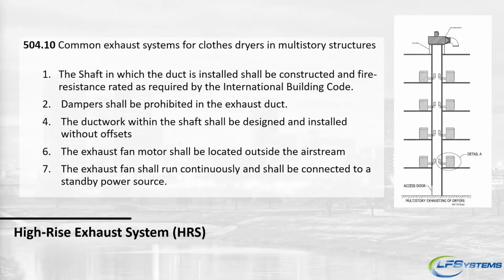The ductwork within the shaft cannot have any offsets. You cannot come up through a building, say 4 floors, and then have an offset and continue that shaft, picking up more dryers. The exception, and this is where it gets into some gray area, is that once you pick up that last dryer, it is no longer a shaft or a vertical ductwork, so you can offset at the roof to then go to your fan. So basically, you just can't have any offsets between your dryers or your hoods.